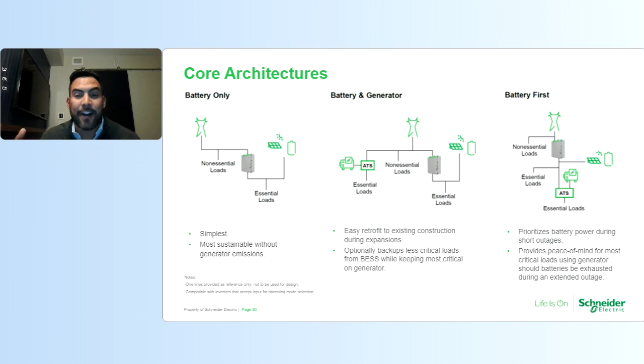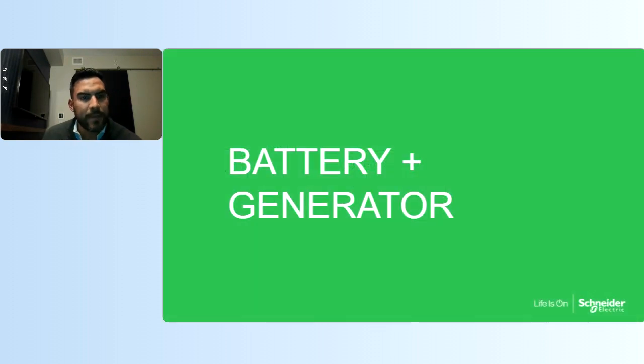If for whatever reason that outage would last longer than 3 to 4 hours, whatever the energy rating that energy storage system is rated for, then the ATS will truly detect the utility outage, right? The energy storage system hits a low battery alarm, and then the ATS will transfer over to the generator. Just to give you some ideas, there's different ways to configure these. If you have a design in particular where you want to go battery first scenarios, there's different ways we can approach it. But these are some of the common architectures that we're familiar with and can support you on these designs. So we'll highlight the middle one there, battery versus generator.